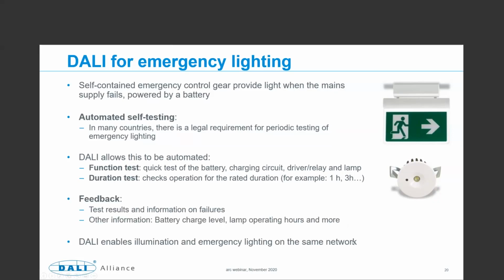And DALI enables illumination and emergency lighting on the same network, so you don't need separate buses or separate networks. It's just one lighting network with all of the DALI devices for general lighting and emergency.